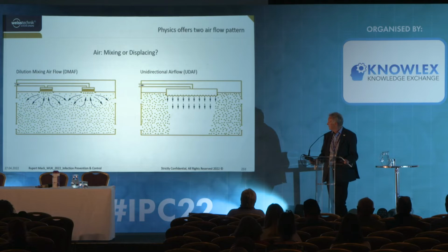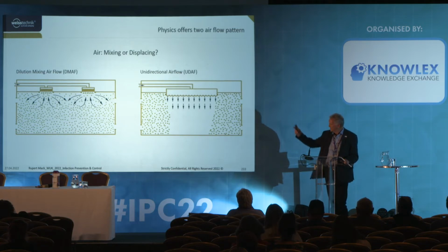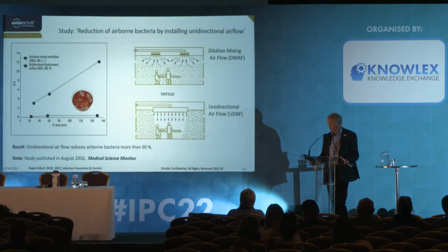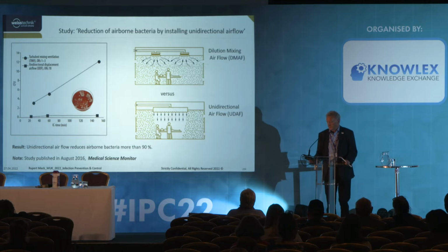The unidirectional airflow shows that you can make sure that you have a protection zone, as you can see here with the dots. The dots are outside of the protection zone, and the protection zone has to cover, according to the standards, the wound area, the instrument tables, as well as the sterile-clothed personnel. So if we follow the ECDC table, there is a must to have filters in the diffusers or in the ultra clean plenum, where HEPA filters are included all over the surface. So the question is, what is the difference between mixing flow and unidirectional airflow in terms of viruses?